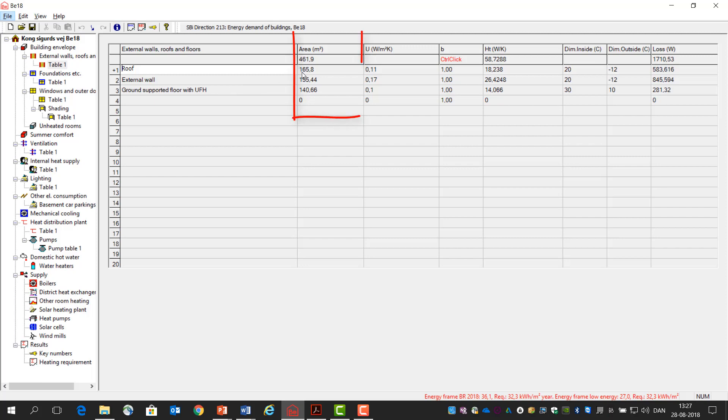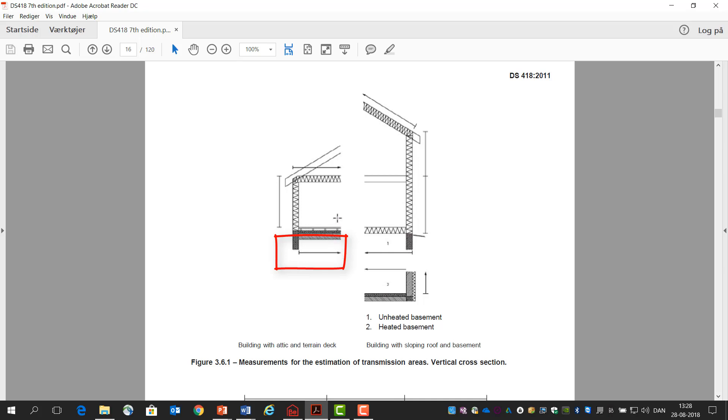Then the first we have to find is the area, and it's different to find the area for the different constructions. For the roof, for example, we take the area—if we go to DS418 we can see for the roof it's external areas, so it goes from outside the external walls to outside the external walls. And for the wall it's from top floor to top insulation.